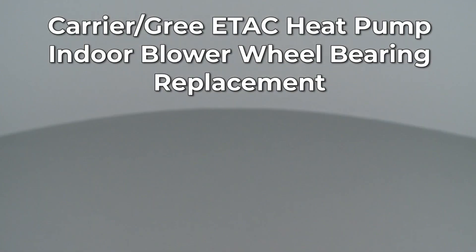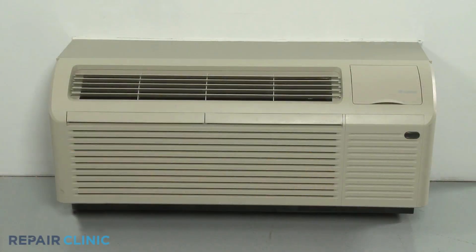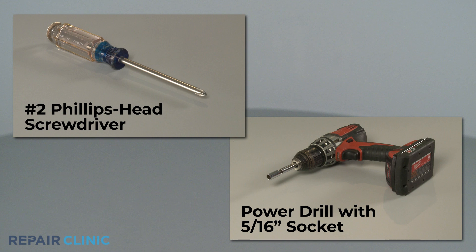Since Repair Clinic encourages you to perform this repair safely, a warning icon will appear when you should use caution. To replace the indoor blower wheel bearing in this Carrier/Gree ETAC heat pump unit, you will need a number 2 Phillips head screwdriver and a power drill with a 5/16th inch socket.